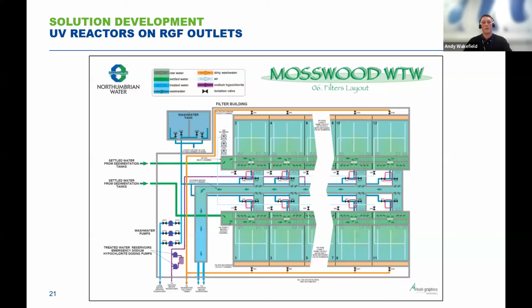So just looking at it in a little bit more detail, essentially we're looking at installing the UV reactors on the outlet pipework of each rapid gravity filter. This would mean that we would have 12 individual reactors, one on each of the individual filters, each capable of doing the filter flow rates, which are in the range of 0 to 20 MLD. It would be suitable for the fact that the filters were the last physical treatment process on site. So the water quality being presented for disinfection by the UV reactors is already suitable, so meeting the water quality regulations in terms of preparation of drinking water before disinfection is applied.